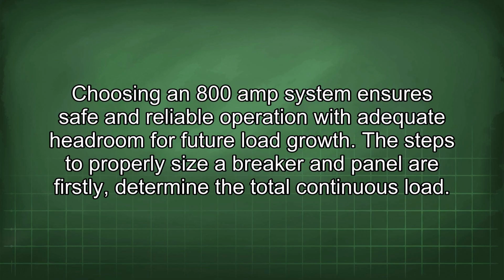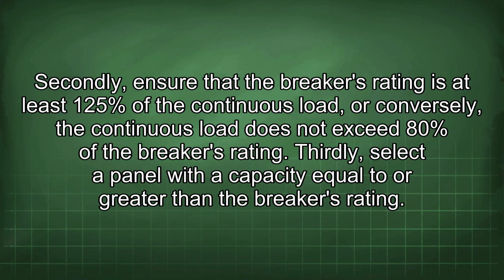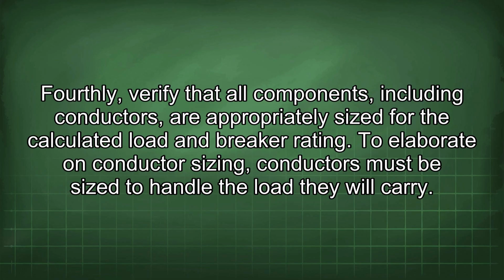The steps to properly size a breaker and panel are: firstly, determine the total continuous load. Secondly, ensure that the breaker's rating is at least 125% of the continuous load, or conversely, the continuous load does not exceed 80% of the breaker's rating. Thirdly, select a panel with a capacity equal to or greater than the breaker's rating. Fourthly, verify that all components, including conductors, are appropriately sized for the calculated load and breaker rating.